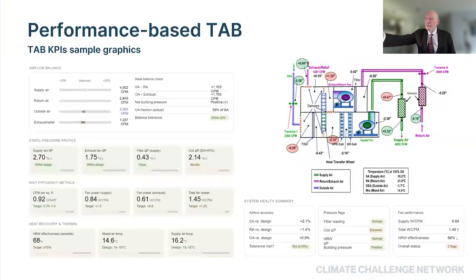These reports show airflows. They show location of airflows. Very often they will come with a photograph, a picture of the air handling unit that is there, so you get a better physical feel for what's where. But the static pressures for us are the critical aspect of these reports that come through. The static pressure drives the fan kilowatts, and the biggest opportunities we find are found within fan systems with excessive fan power for the same amount of airflow. There's no value being produced.